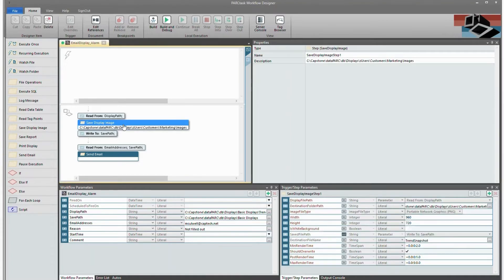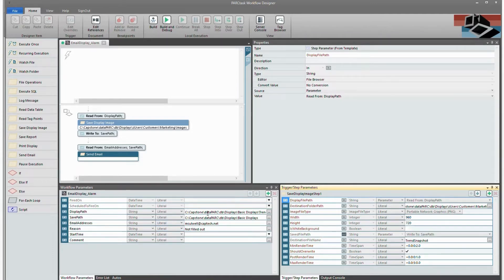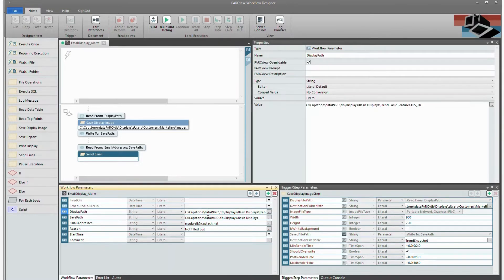The first step is to save a display image, and then secondly, we're going to send an email. Each of these steps has a variety of parameters that we'll use. Some are hard-coded in, and others are drop-downs from the left-side parameter field. These are the parameters that we'll want to be able to edit in the alarm configuration so that we can assign different displays for different alarms. Any parameter that we want to edit in alarm configuration, we need to check off as PARCview Overridable.